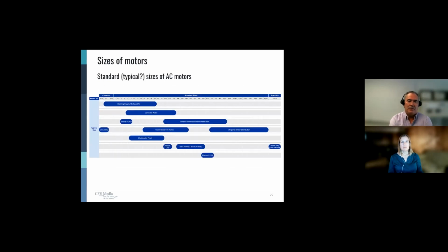So here's a graph I just put together to give us a spectrum of the sizes of motors we see in the world. This is not meant to be inclusive at all, but it gives us a feel for the sizes and what they do. If we start at the far left-hand side, in a commercial building with a water system or exhaust fan system, we'll see very small motors, just used to circulate water or run exhaust fans in restrooms. They can be sub half horsepower, below 1 horsepower. And then as we move to the right, we see the things we typically run into.